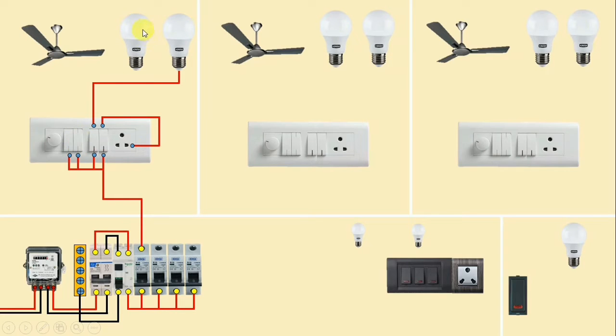But you should know that when making your distribution and connections, for each of the lighting you want to make sure the lighting has a different circuit breaker, and the socket outlet also has a different circuit breaker. So as you can see, I'm just extending the lines from one of the miniature circuit breakers.